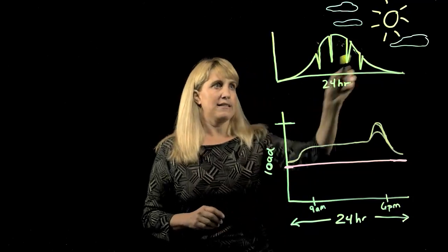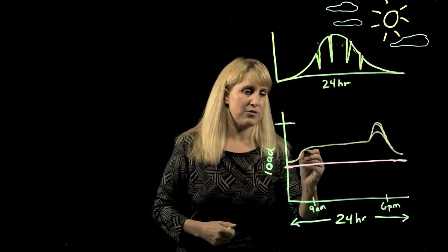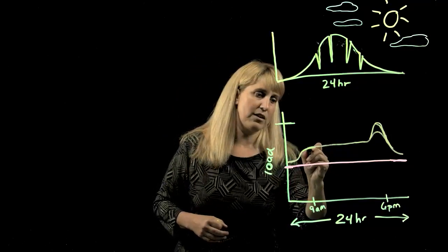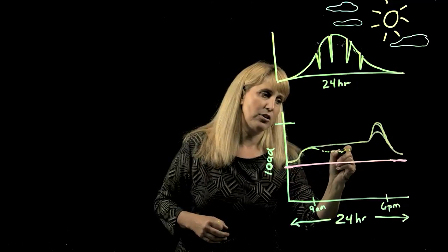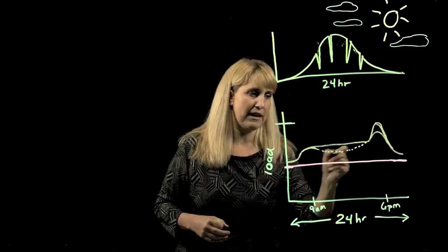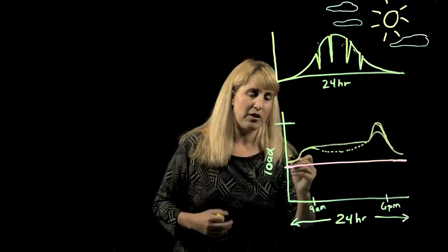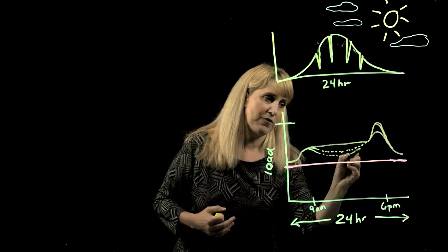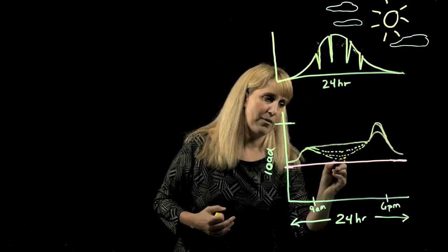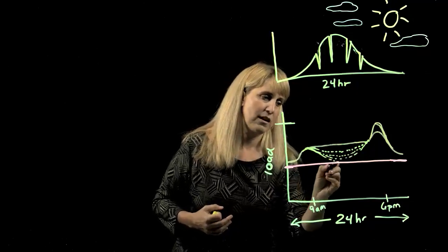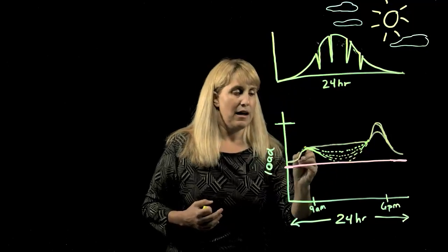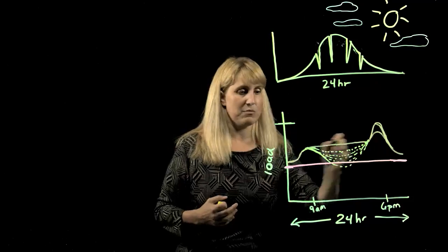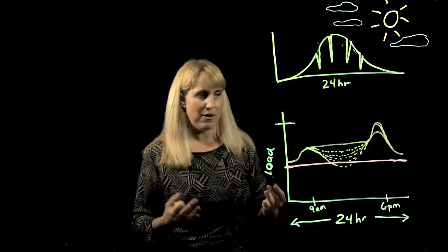On a large grid, this net impact of solar energy is going to look to a grid operator like basically a decrease in the overall load demand for that particular market during that time when the sun is available. And if you start to add a lot of this, it can really start to become difficult to manage for grid operators. As you add more and more solar, you start to see a reduced demand from these more conventional sources of central power stations.